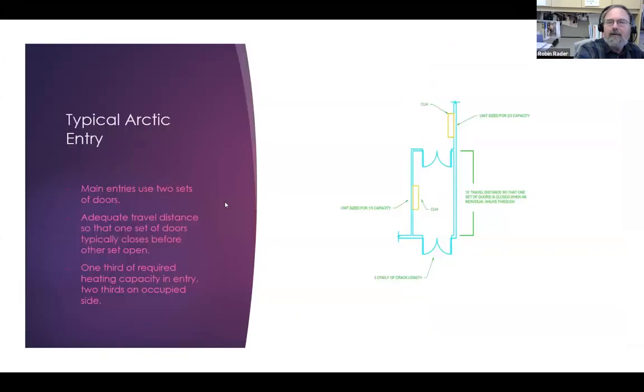So I'm going to talk about Arctic entries a little bit. A typical Arctic entry has 2 sets of doors, and they have adequate travel distance between the doors so that typically one set of doors is always closed. So when you calculate the heat required for this entryway, the way you do it is you multiply 3 times the square footage of the door panels.